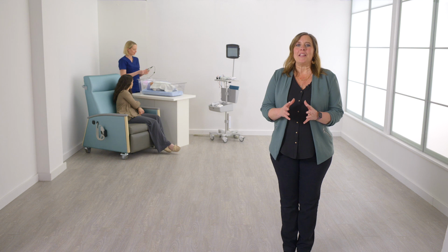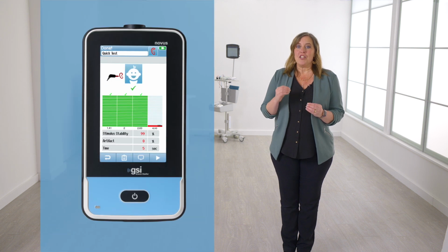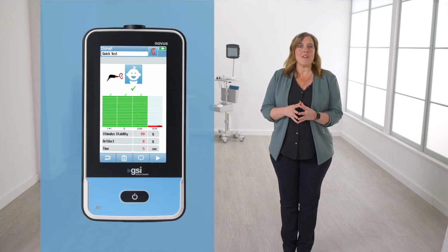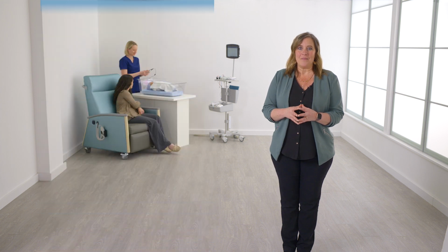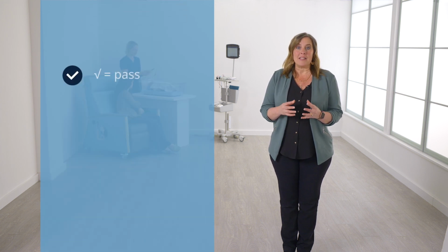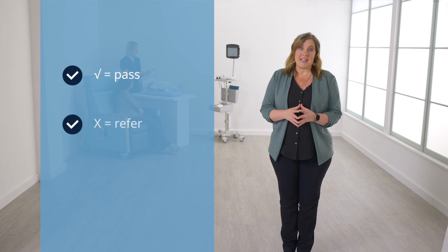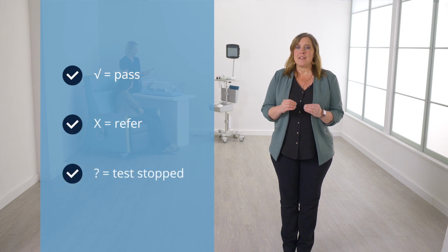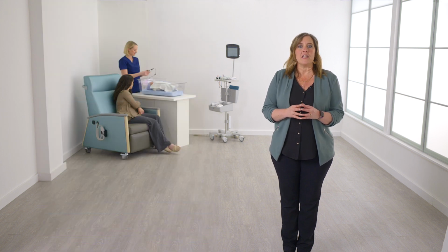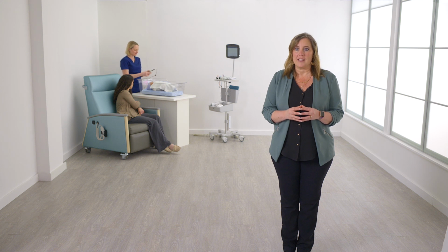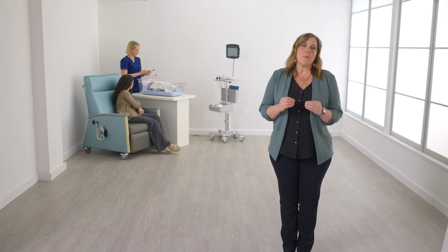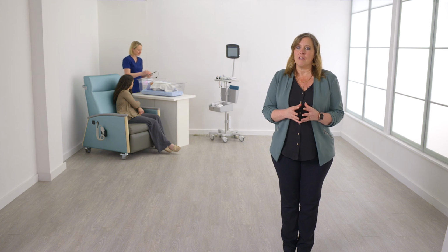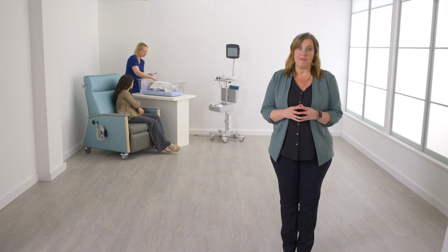When the test is complete, a result will be assigned. A green check mark in the center of the screen means the infant passed the hearing screening for that ear. If a yellow X appears, that means the infant referred or did not pass the test in that ear. If the test is stopped manually, a black question mark will appear, which indicates an incomplete test result was obtained. Follow your facility's newborn hearing screening protocol for next steps. To avoid person-to-person cross-contamination, the ear tips are intended for single patient use only and must be disposed of immediately after the screening.